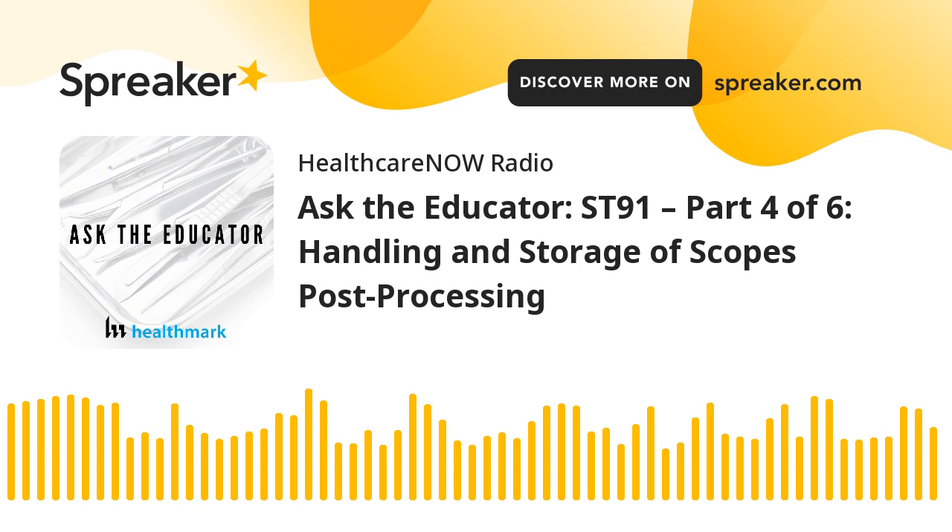There was some reserve storage right there in the procedure room, so it's a good idea to get away from that considering what happens in a procedure room. When standing in the decontam space of an endoprocessing area, I remind people: assume this whole room is contaminated, because it is, because of the aerosolization that occurs from manual washing. You need to pay attention to that for anything else in the room. The dirty-to-clean flow matters. The separation of spaces matters. An endoscopic procedure room also has aerosolization and contamination—that's why we need to not have patient-ready scopes stored in there.